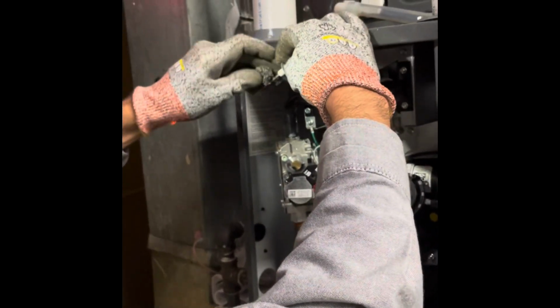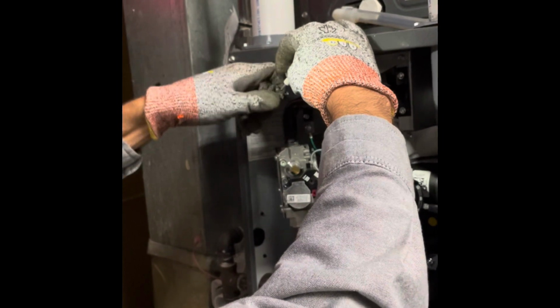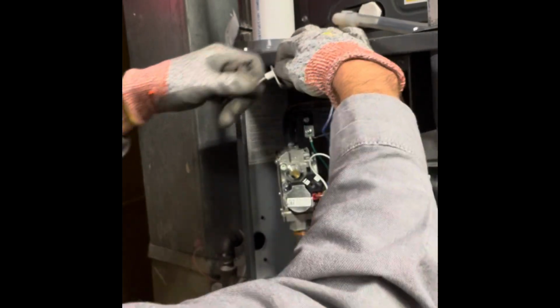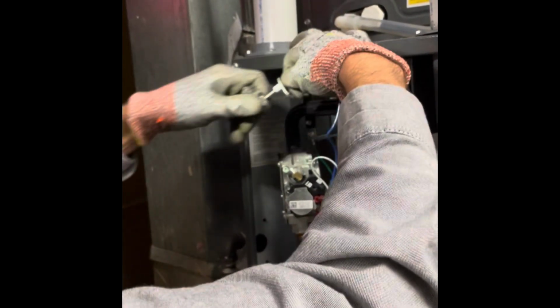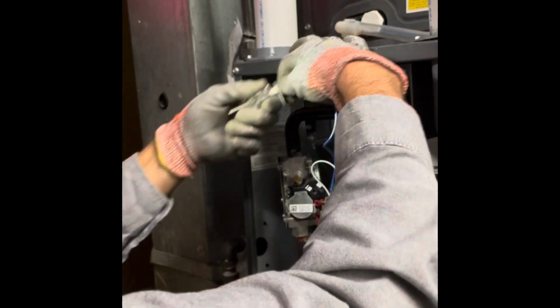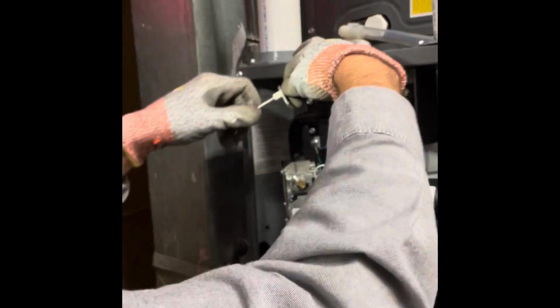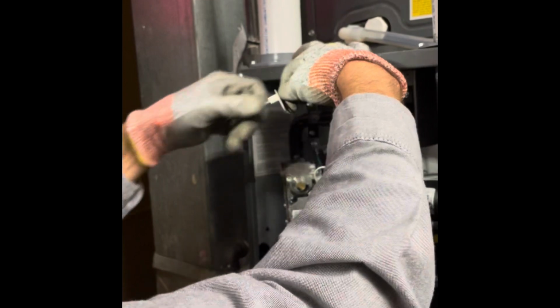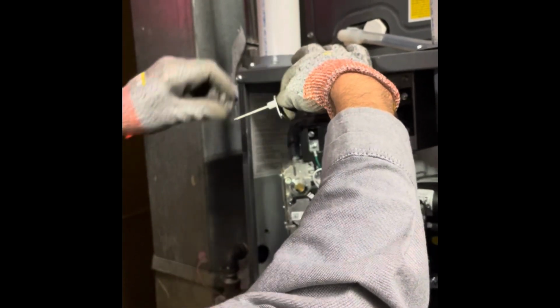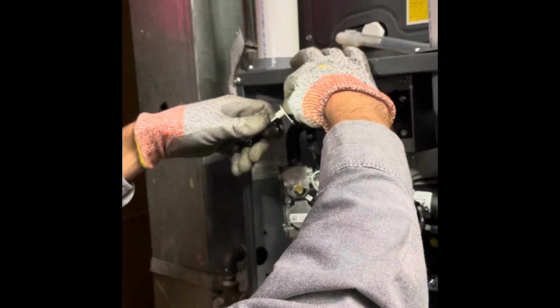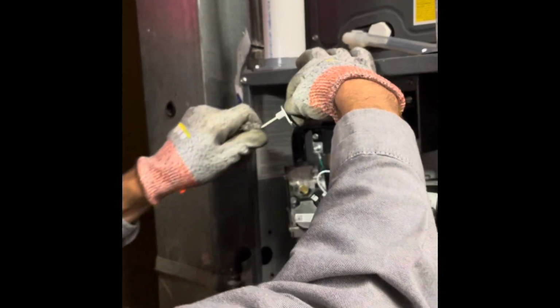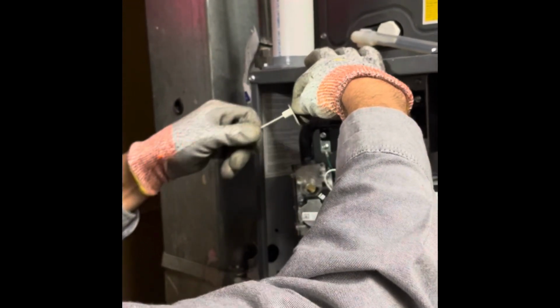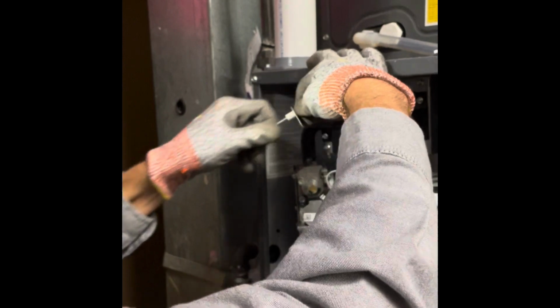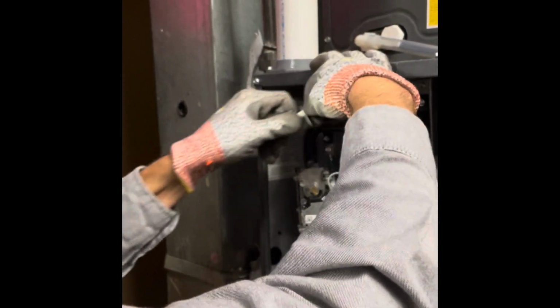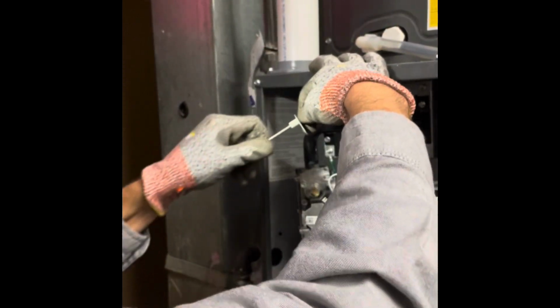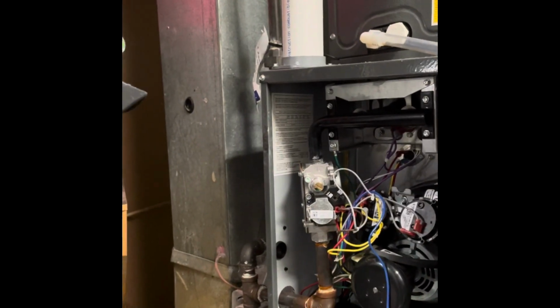That's because it failed the safety. The flame sensor didn't get satisfied, and the gas valve won't stay lit or stay open. So fine steel wool is the go-to for this. Don't ever use sandpaper on these rods. Sandpaper scratches the rod and it'll collect the carbon three times as quick. Some out there where the guys use sandpaper were getting flame rod failure within a month of operating that furnace. All right, so our flame sensor's clean.